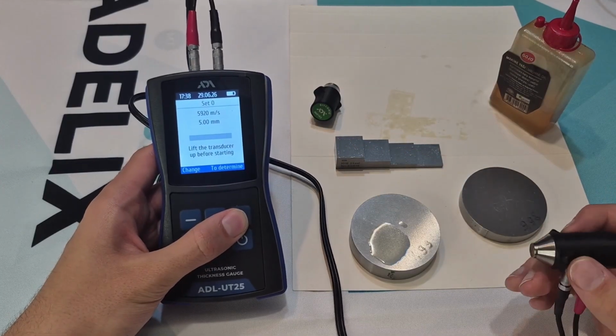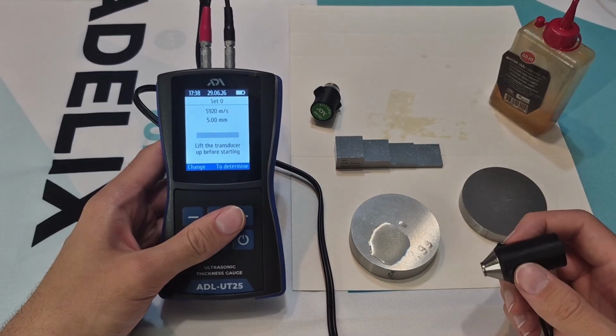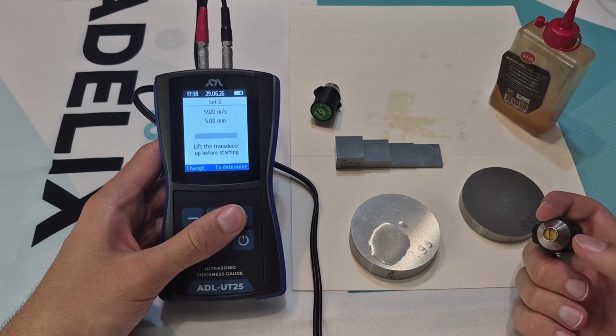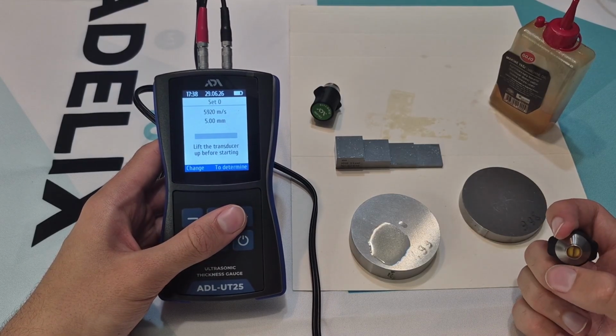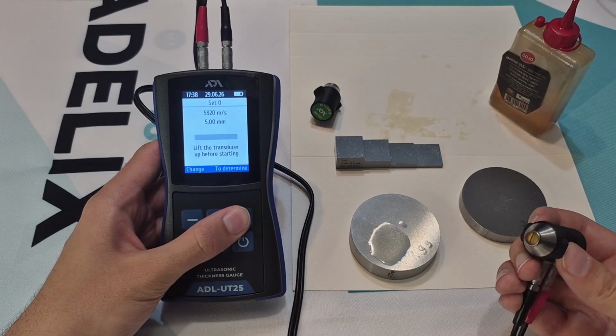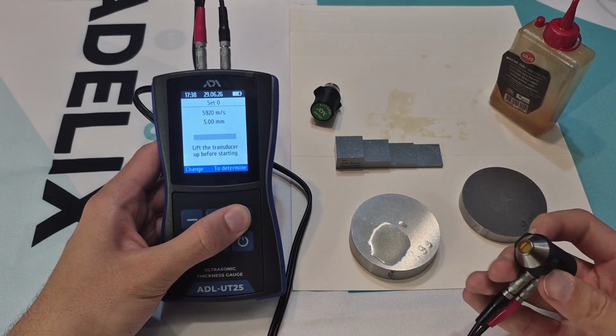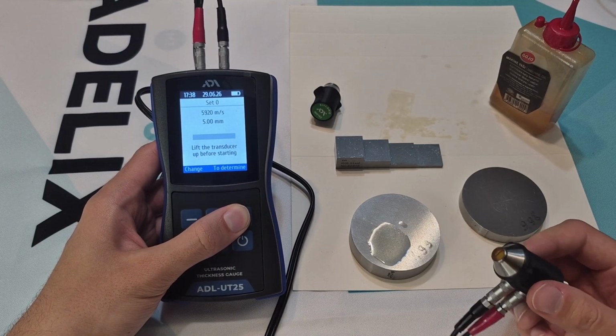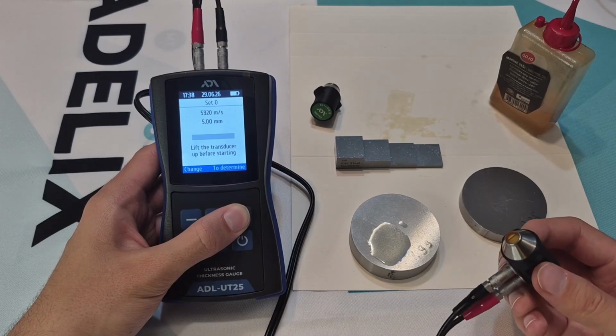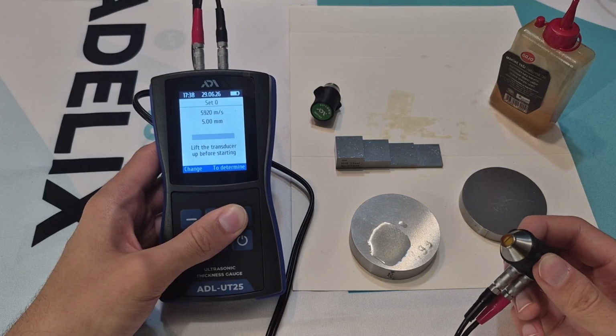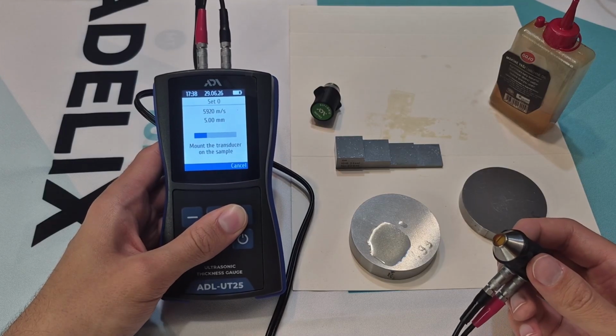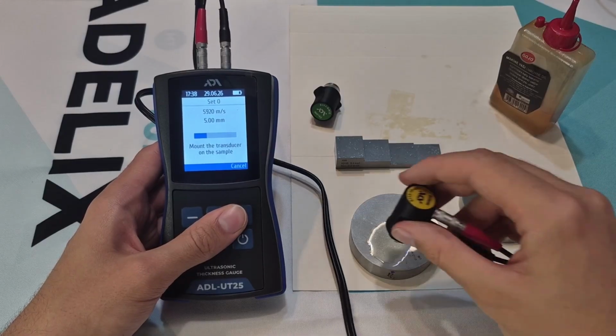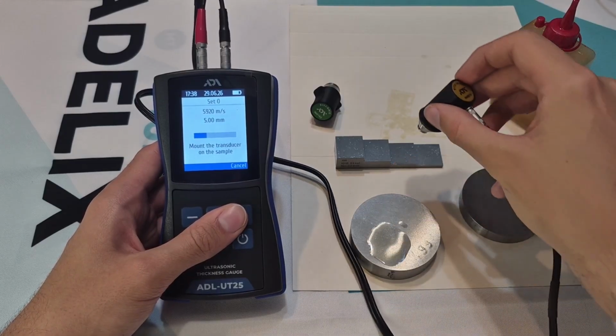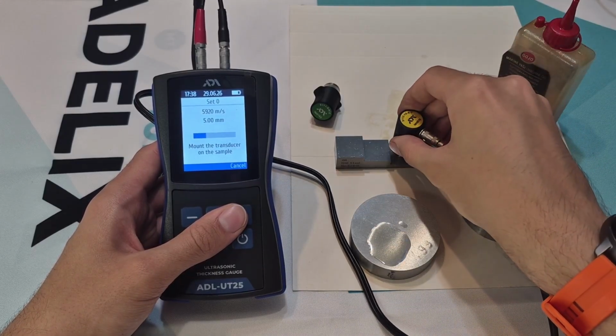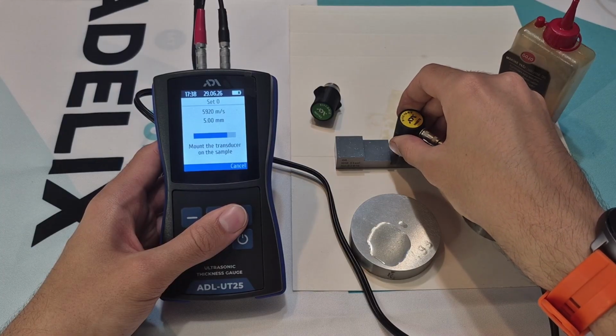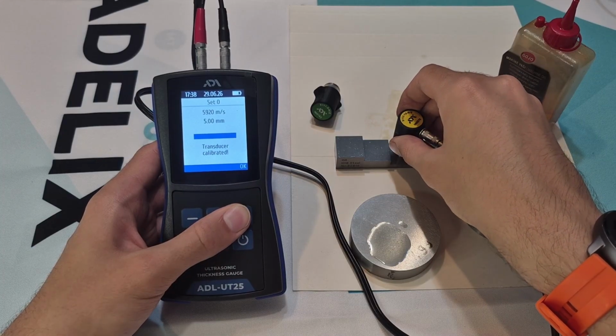After entering the required parameters, we press Save. We check once again that the working surface of the transducer is dry. Now we press Detect while the transducer is in the air and not touching the surface. After that, we place it on the sample and wait for the procedure to finish. When it is finished, we press OK. As you can see, the device correctly determined the thickness of the sample.